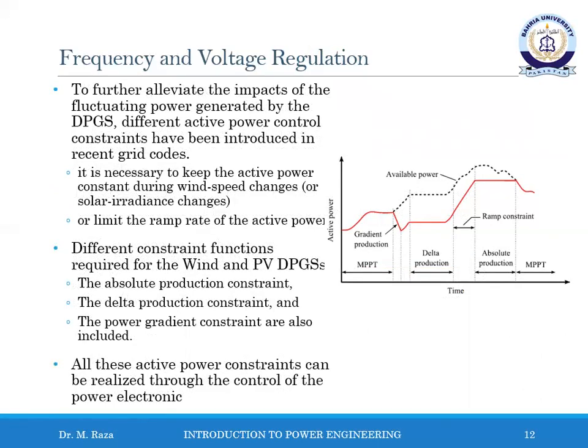Different constraint functions are required for the wind and PV distributed power generation system, such as the absolute production constraint, the delta production constraint, and the power gradient constraint. These active power control features or functions are defined in order to prevent the instability or overloading of the distributed grid. An absolute production constraint is used to avoid overloading, and the active power output of the wind farm is constrained to a predefined megawatt.